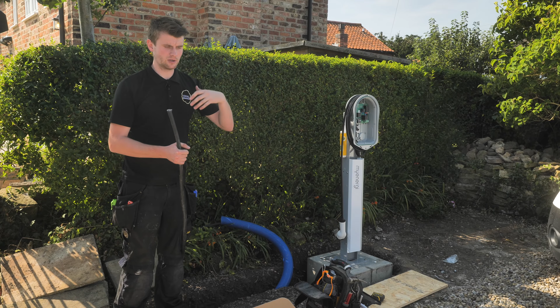We can connect the grid CT clamp back in the house. That grid CT clamp will monitor what the home is using, and therefore we can add some grid protection onto it. So we can set within the Zappi not to allow the main supply to breach 60, 80 or 100 amps, depending on what our main fuse size is, and we can connect that within the garage and feed it back down this Cat 5 and into here.